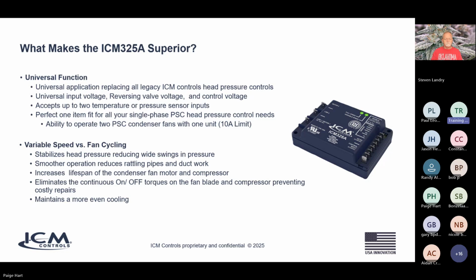So let's look at variable speed versus fan cycling. Why would you want the ICM325A that is variable speed versus just a typical cheap old fan cycling control? Well, variable speed stabilizes your head pressure and reduces wide swings in the pressure. Wide swings in pressure are completely unacceptable in grow houses and places like that, where you need to maintain a more consistent temperature overall.